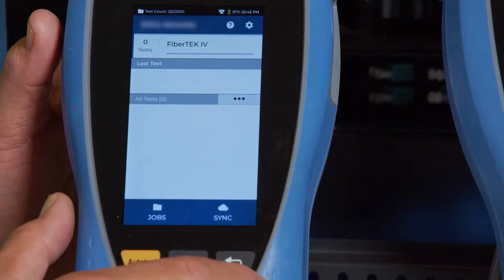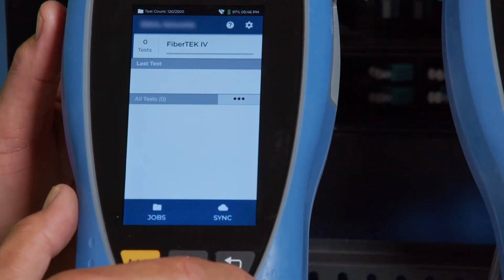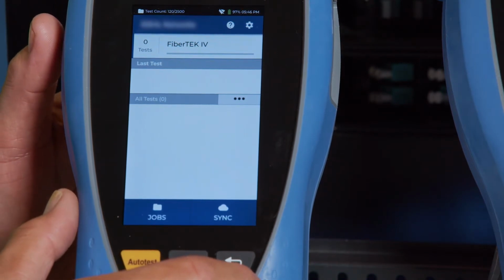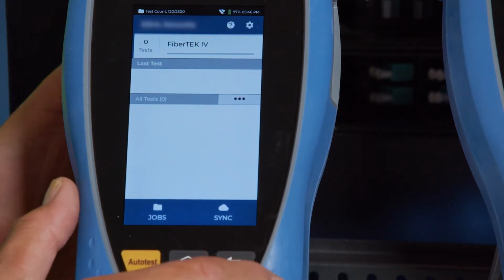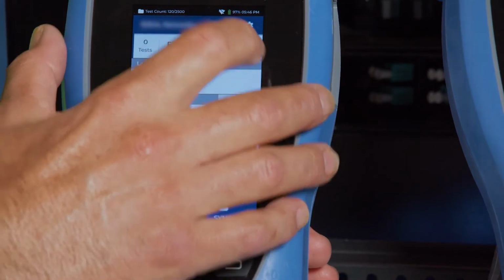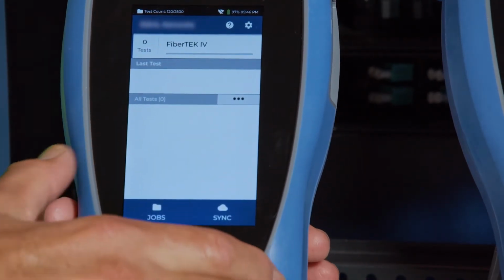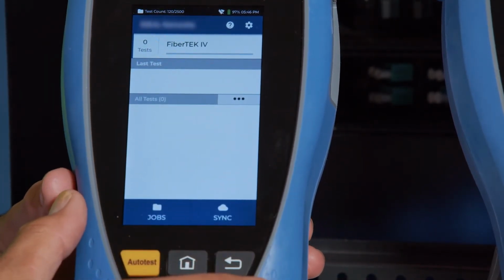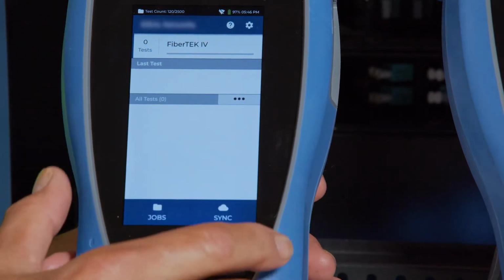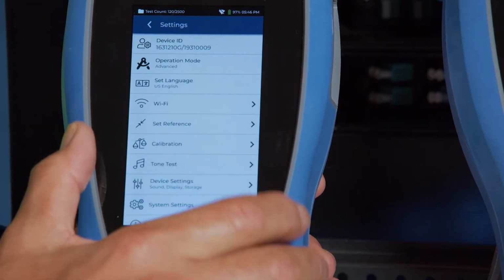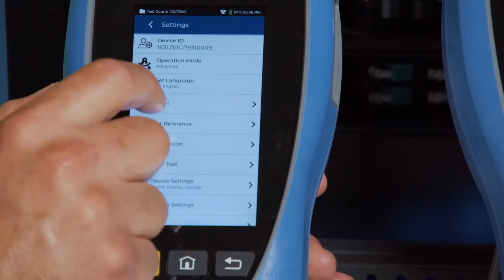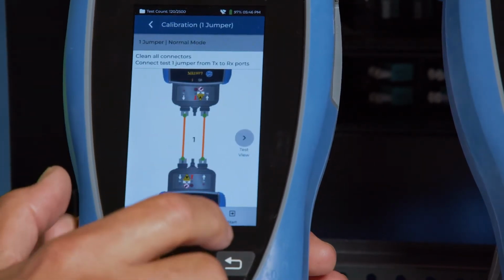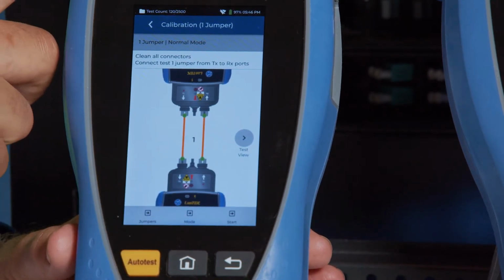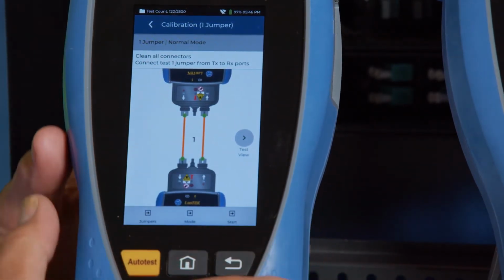After we've let the handsets power up for at least 5 minutes, we'll go ahead and perform the field calibration or set reference. In the user interface, we call it a set reference. We use the term set reference field calibration interchangeably. To get to that menu, you hit the preferences icon in the upper right hand corner and then press set reference. And when the FiberTEK module is attached, you'll be presented with this diagram.